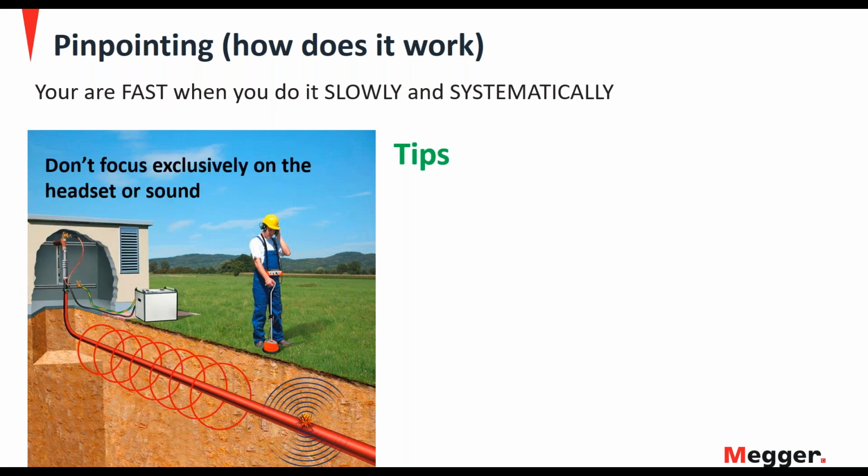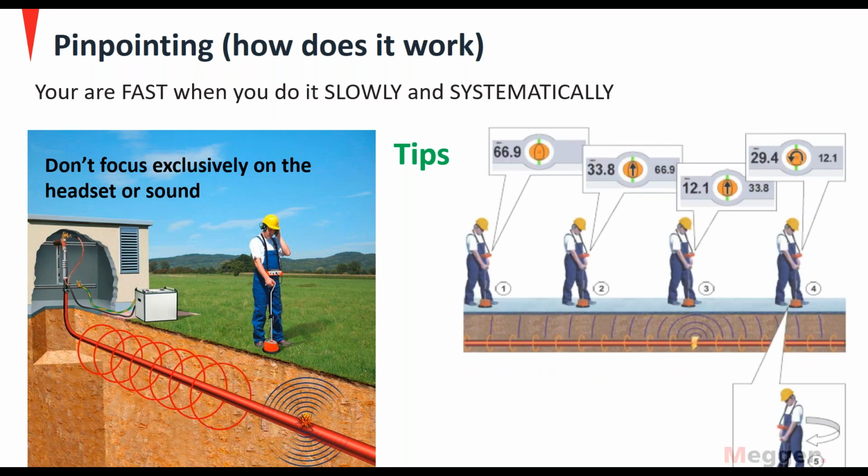What you don't want to do is focus exclusively on the headset or the sound. Yes, it does amplify the sound of the thump. And yes, you can actually pinpoint a fault that way. You can listen your way down to the fault. But we don't want to just listen. The Digiphone is giving us much more information than that.